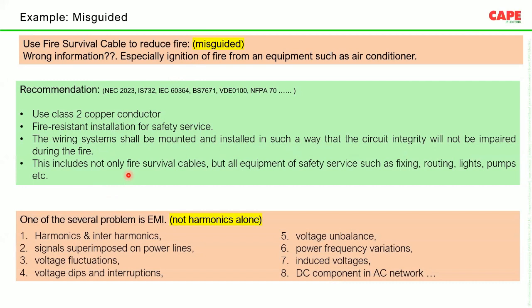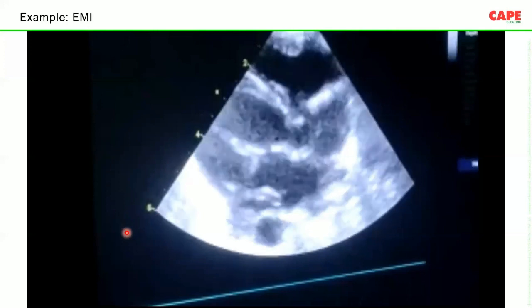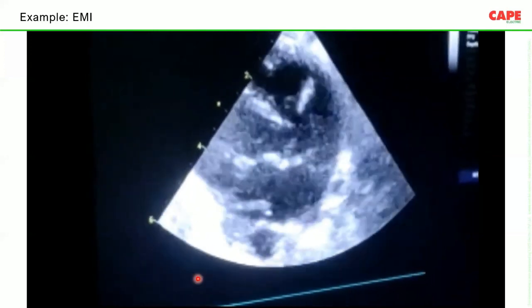Another issue is EMI. I would say harmonics is one of the subjects in EMI, especially in hospitals. There are several issues: harmonics and interharmonics, signals superimposed on power lines, voltage fluctuation, voltage dips, voltage unbalances, power frequency variations, induced voltages, and so on. There are several issues because in a hospital, a lot of equipment is used. This particular video, you can see.